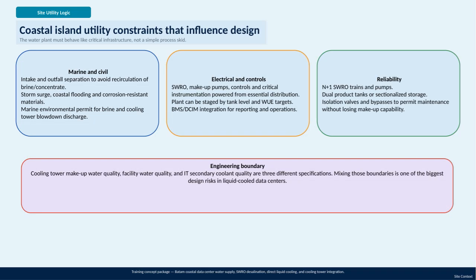Let's talk about the site utility logic for this coastal island data center water supply project. First, it's important to understand that the water plant here must function like critical infrastructure. It's not just a simple process skid. This means it has to be reliable, robust, and fully integrated into the overall utility system. Starting with site context, there are marine and civil constraints we have to address. For example, the intake and outfall need to be separated to avoid recirculating brine or concentrate back into the system.